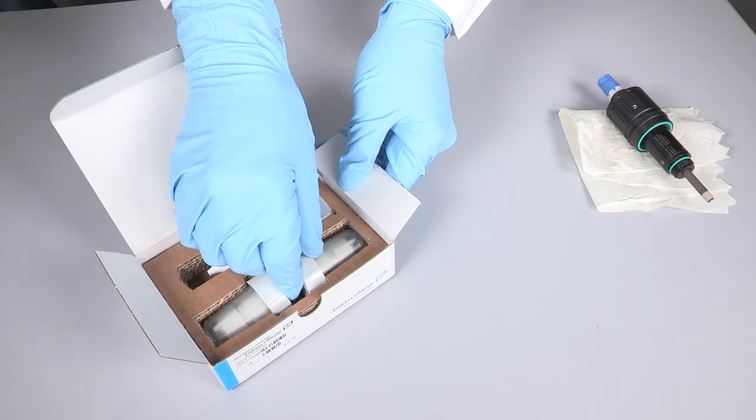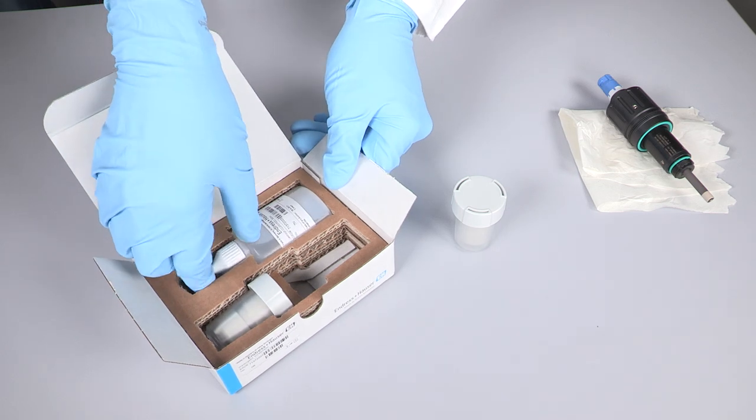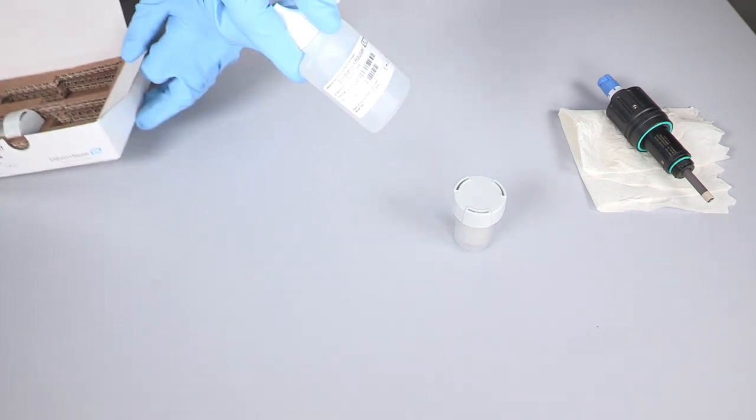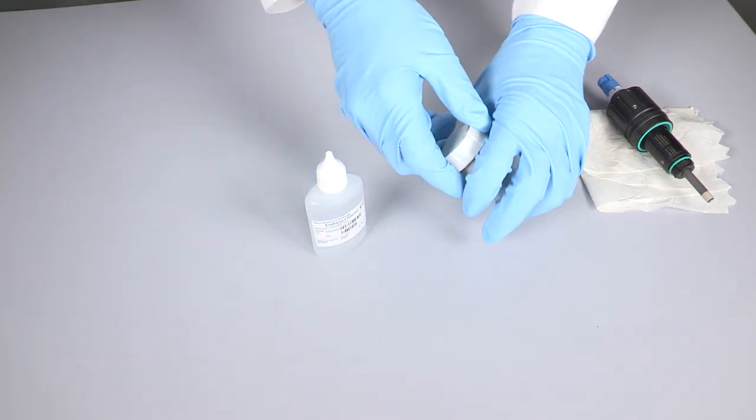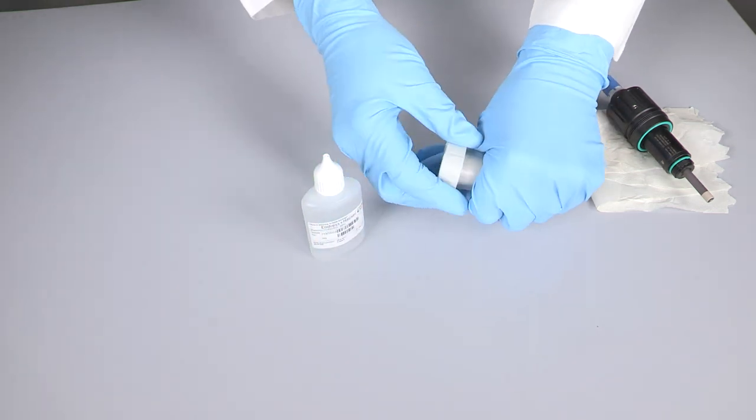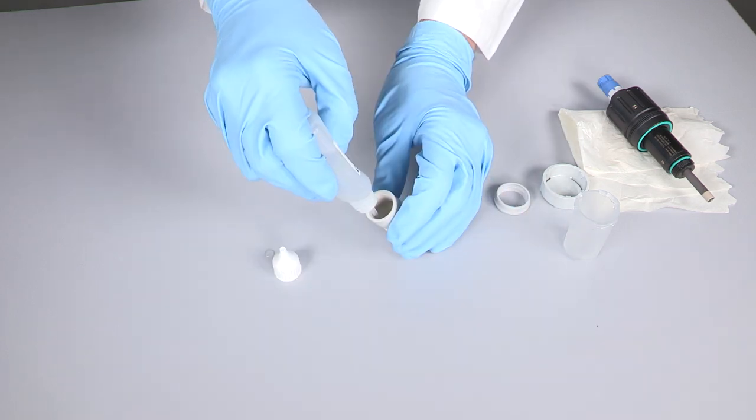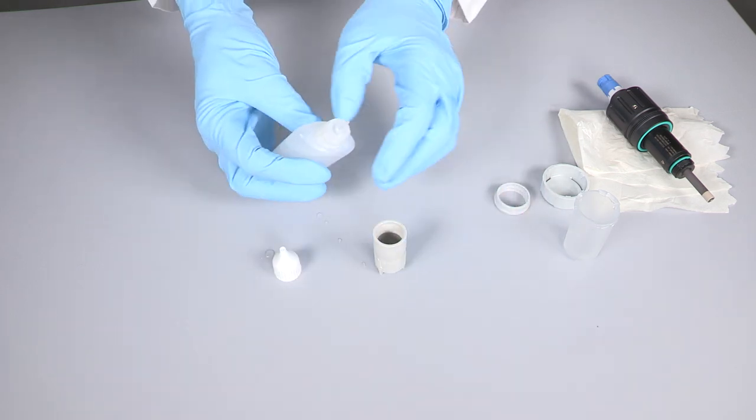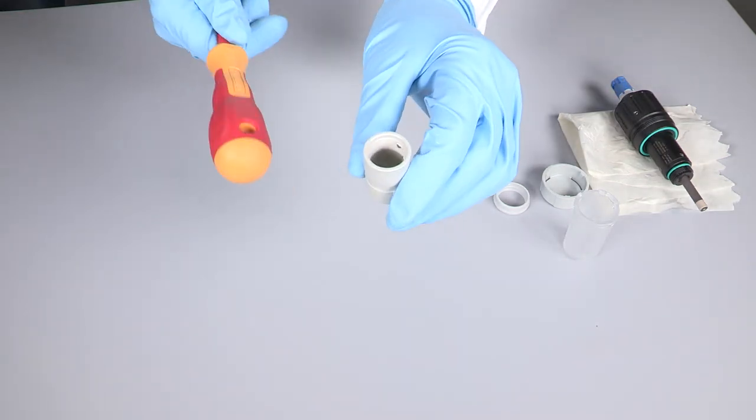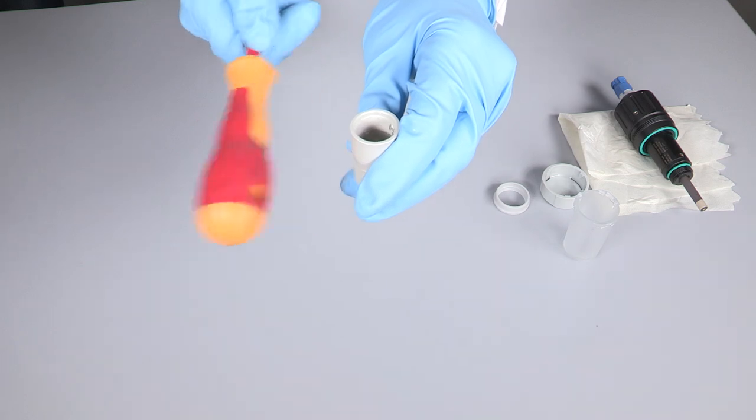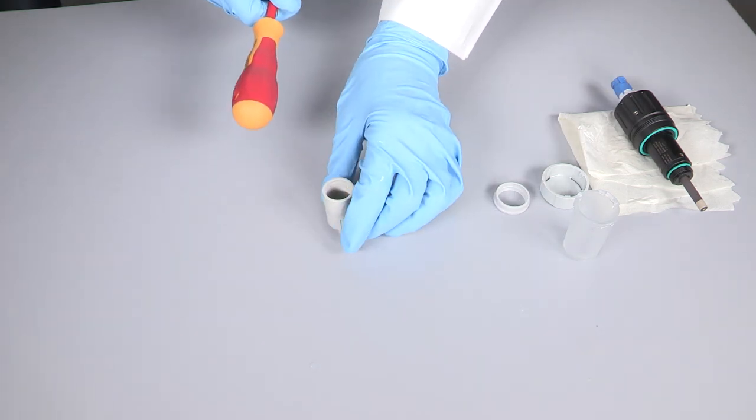Now we replace the membrane cap and the electrolyte solution. Take care that you do not use expired electrolyte, so check the date on the bottle. Fill electrolyte into the membrane cap until the start of the internal thread. Remove the gas bubbles from the electrolyte by knocking gently with a hard item, for example with a screwdriver, against the membrane cap.